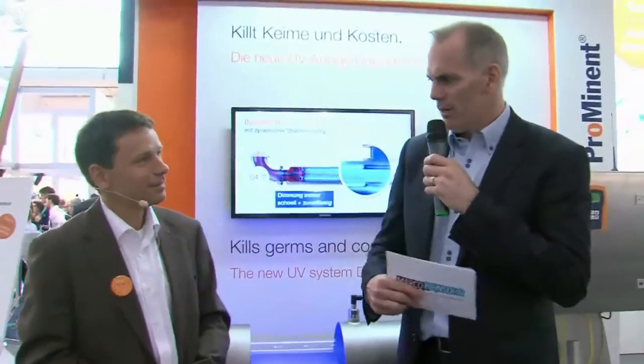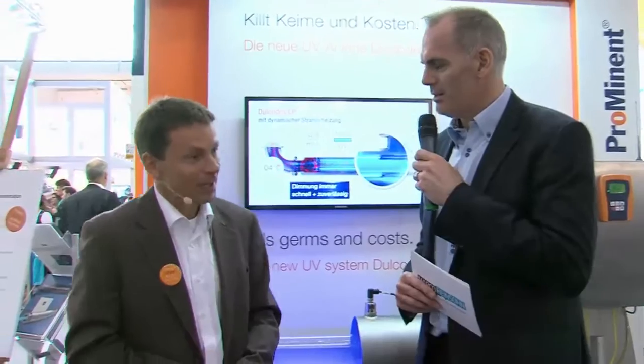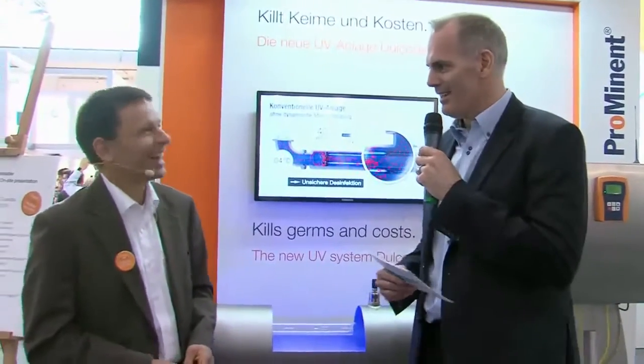That sounds familiar — if I'm freezing or getting too hot, I don't work effectively either. So what did you do to find a solution? We had a great idea: we were able to wrap a heating element around the amalgam. The amalgam is an important part of the lamp which we have to keep at the right temperature. We wrapped the heating element around it, and whenever the temperature gets too low or too high, we control the temperature of the amalgam to always be in the optimum temperature range. That's like turning on the heating at home when it gets cold outside.